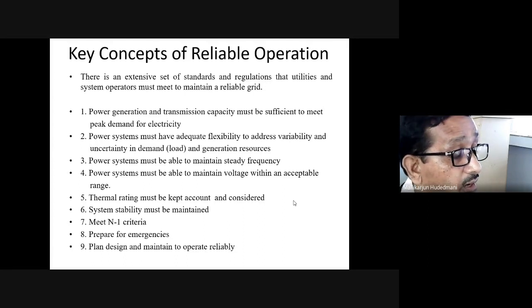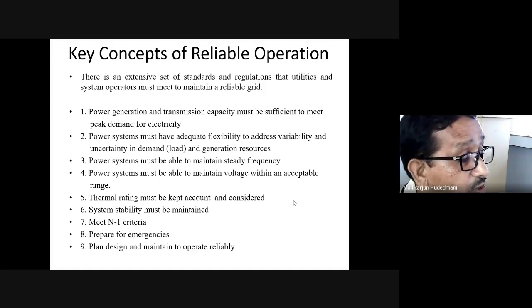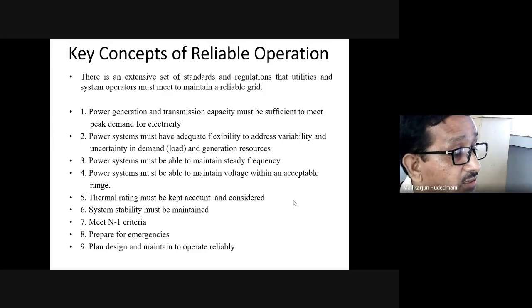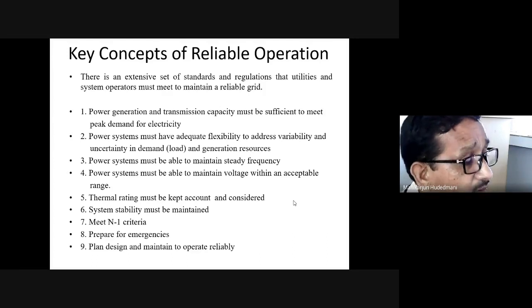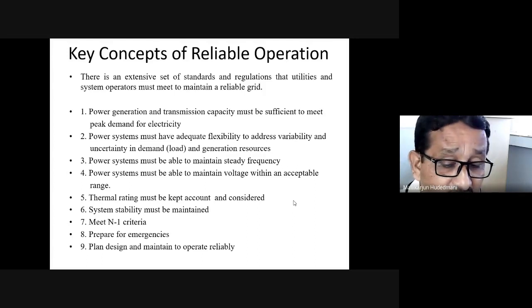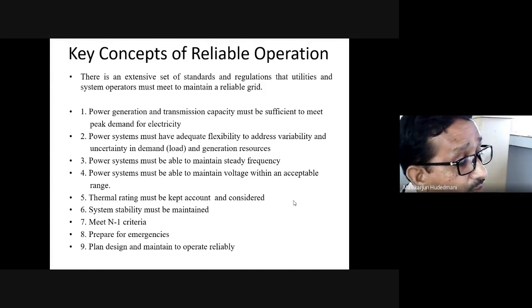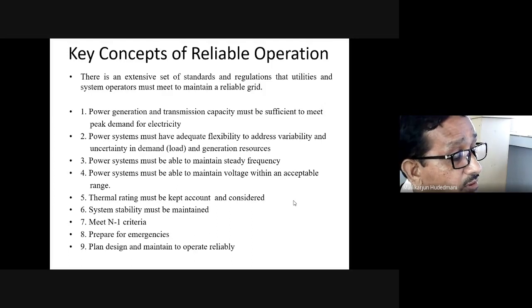When I look at this parameter, economics of operation: how economic is this particular generator right now? Over a day, the next 2 days, the next 1 week, if I project it, whether it is costlier or cheaper to produce a megawatt from it. When I take a decision, I must be capable of removing it if it is costlier, and if it is cheaper, accelerating it and making it generate more and more. I should have flexibility. In that way also you can see.